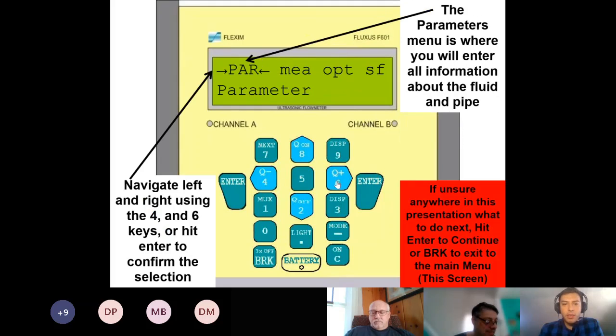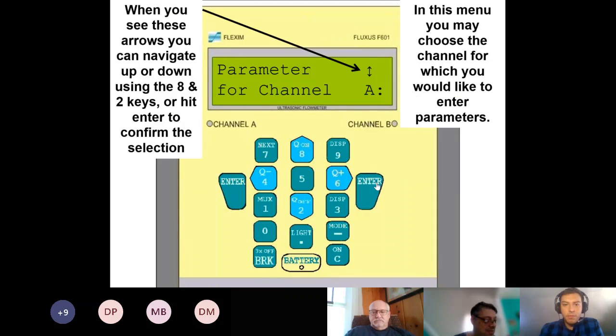But when you want to get started metering something, you would start with the parameters. You'd go into parameters and you would hit enter. Make sure that you're in channel A. If you want to measure on channel B, you hit the 8 or the 2. You'll notice they're lighter blue. So we'll start with A.